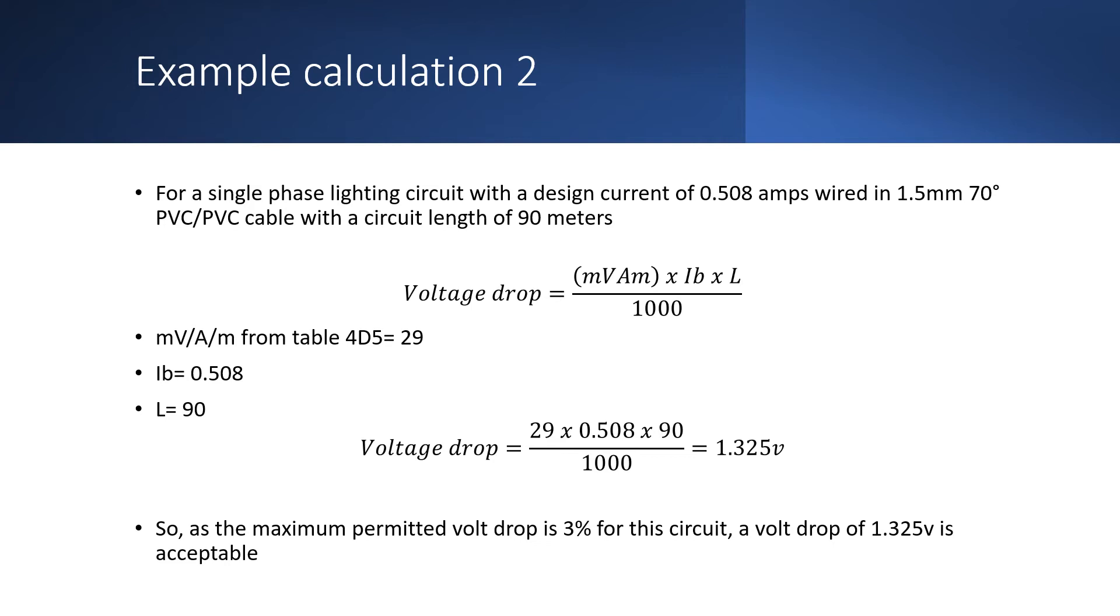So the equation becomes voltage drop equals 29 multiplied by 0.508 multiplied by 90 and then divided by 1000, and this comes to 1.325 volts. So as the maximum permitted volt drop is 3% for this circuit, a volt drop of 1.325 volts is acceptable.